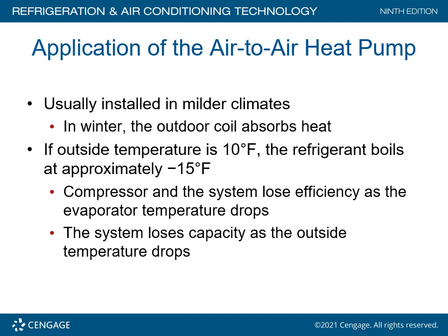The compressor and the system lose efficiency as the evaporator temperature drops. The system loses capacity as the outside temperature drops. So if you end up with minus 30 degrees in wintertime, I would very seriously question the installation of a heat pump system to heat the structure, because as the outside temperature drops, it's very inefficient at supplying heat to the inside without utilizing a secondary source or auxiliary heat.